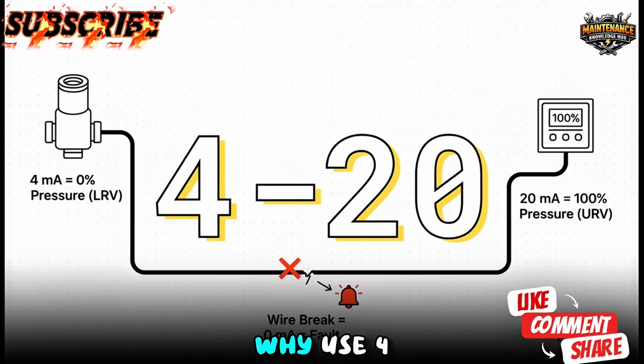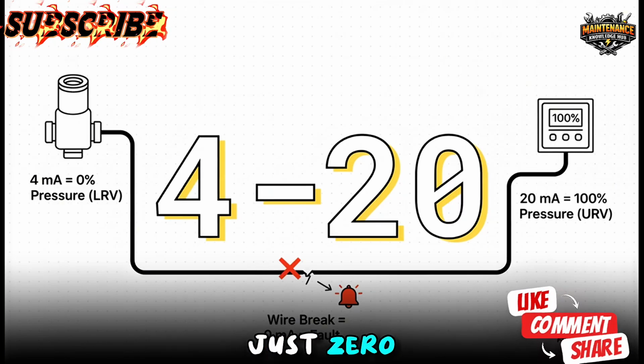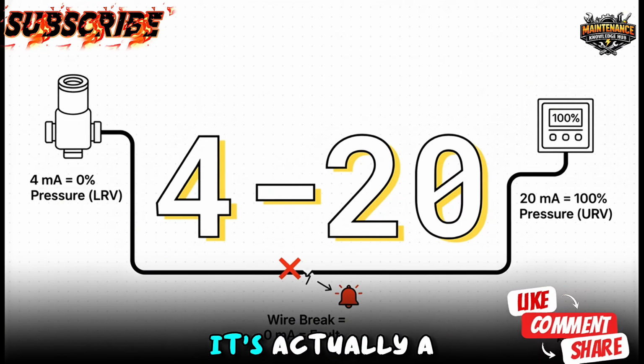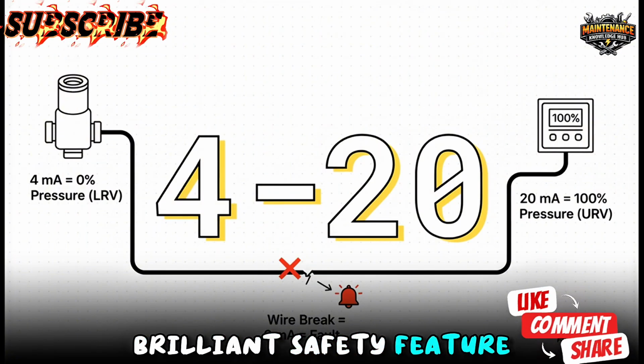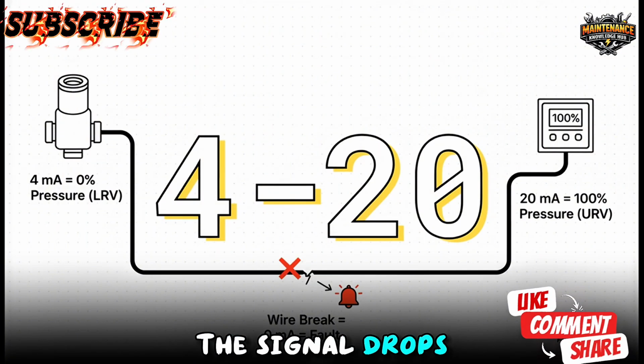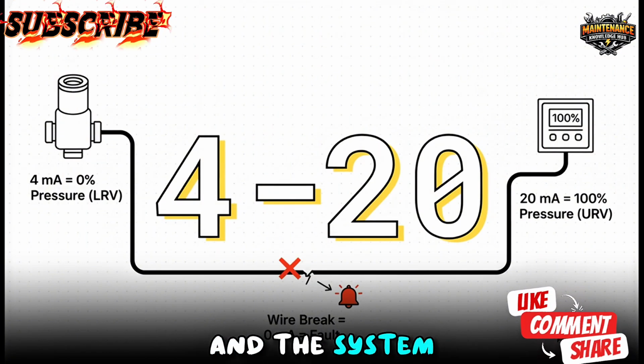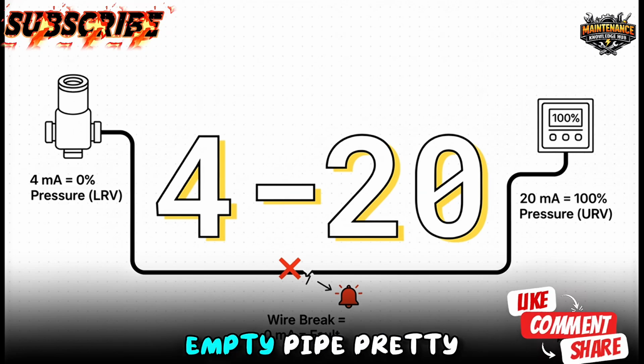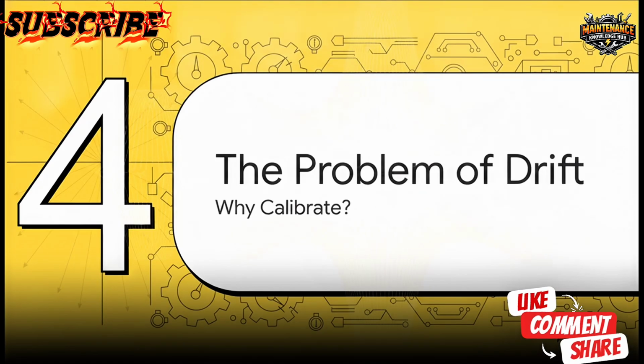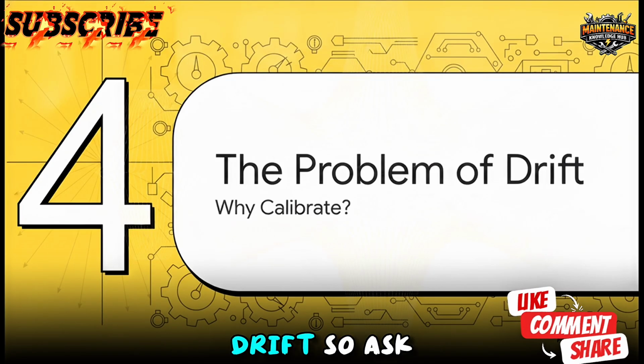Now, you might be wondering, why use 4 milliamps instead of just 0 for 0 pressure? Well, it's actually a brilliant safety feature. If a wire suddenly breaks, the signal drops all the way to absolute 0, and the system instantly knows there's a fault, not just an empty pipe. Pretty clever, right?